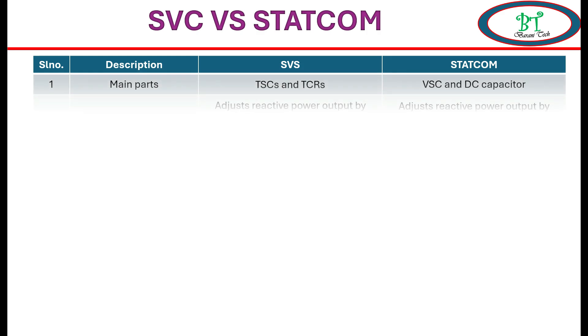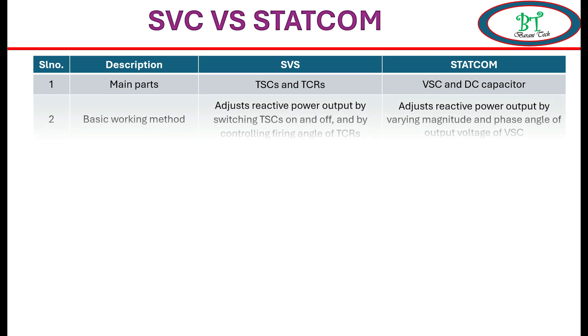Second, the basic working method for SVC is adjusting the reactive power output by switching the TSC or TCR, whereas for STATCOM, adjusting the reactive power output by varying the magnitude and phase angle of the output voltage of VSC.